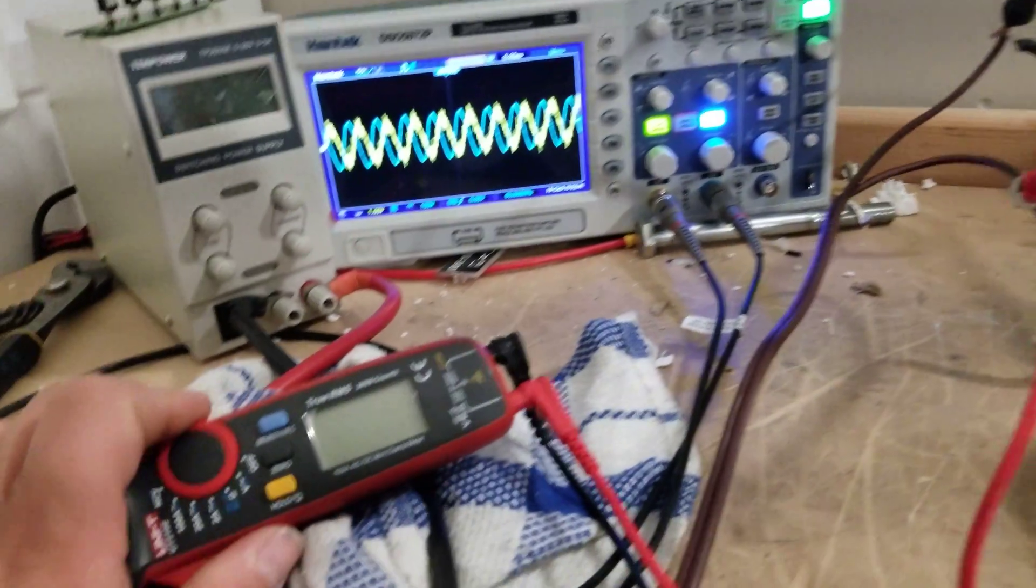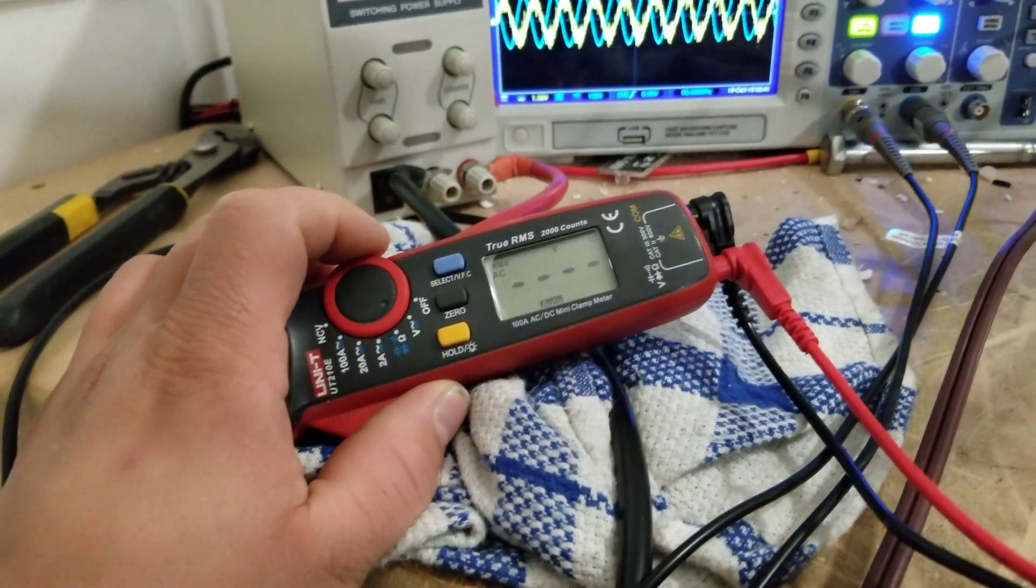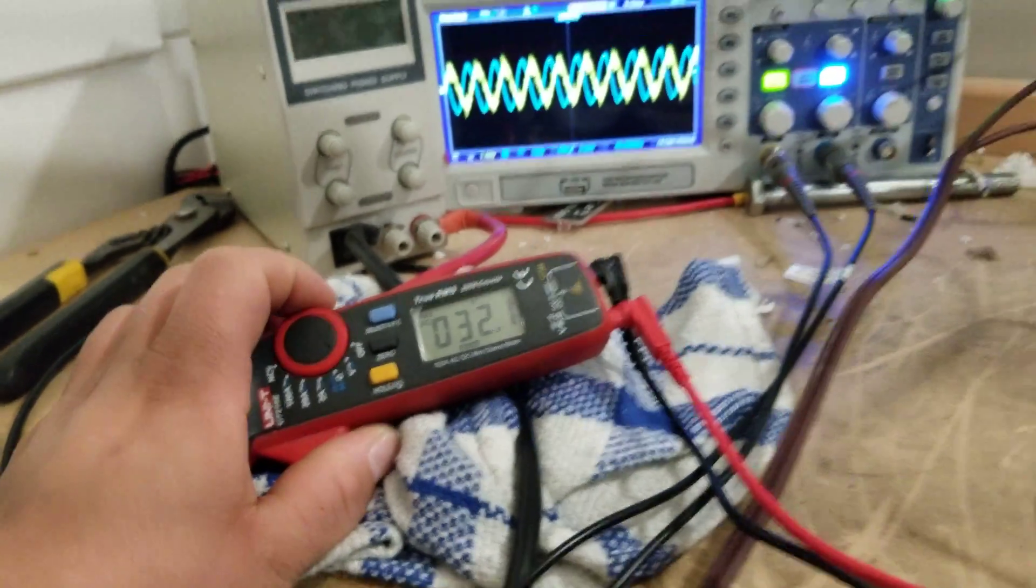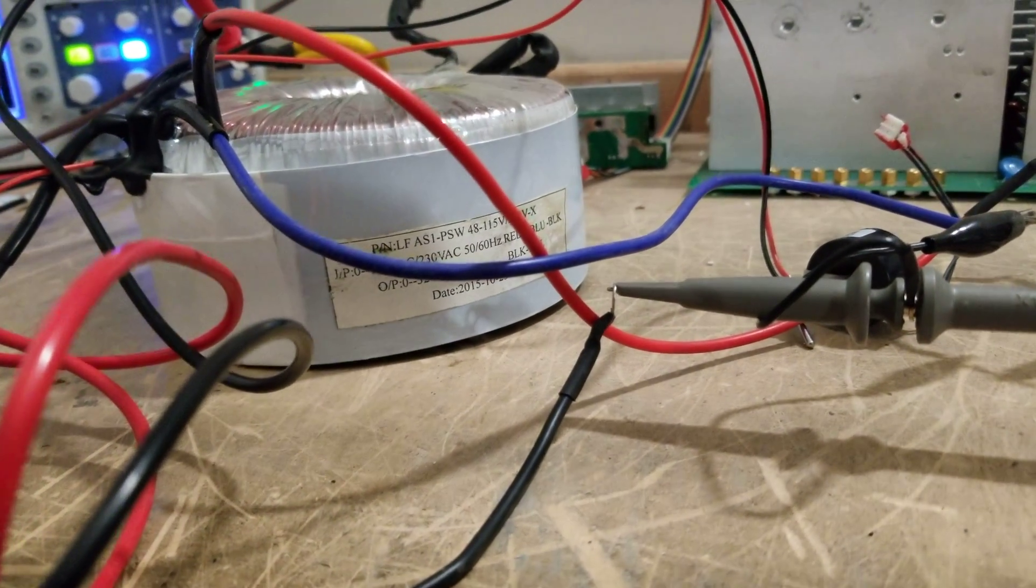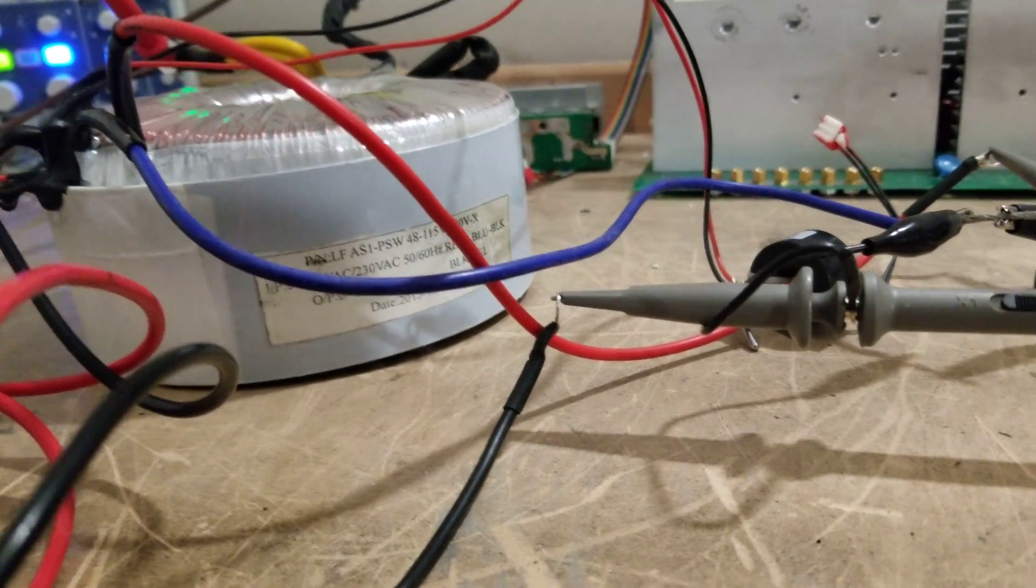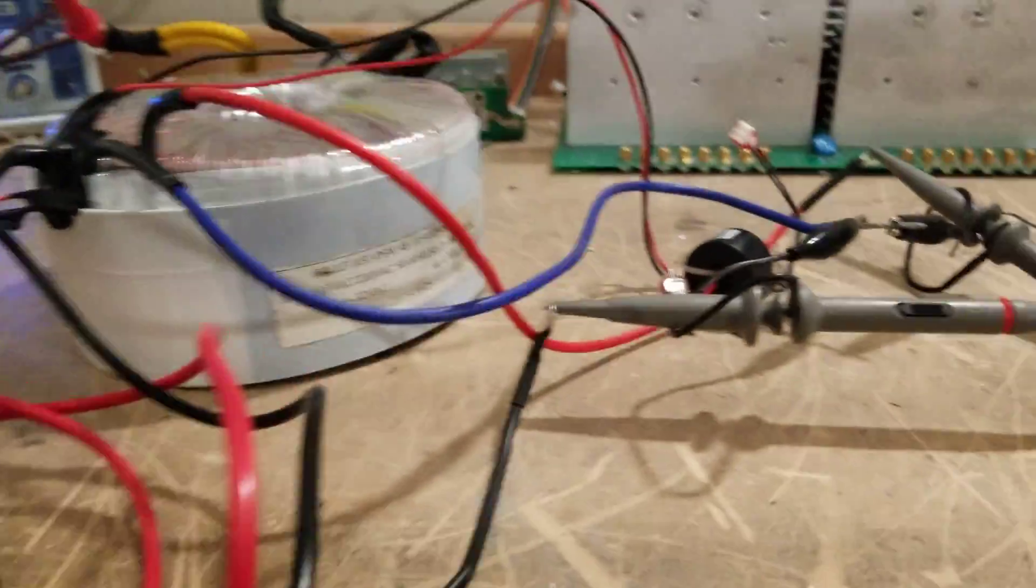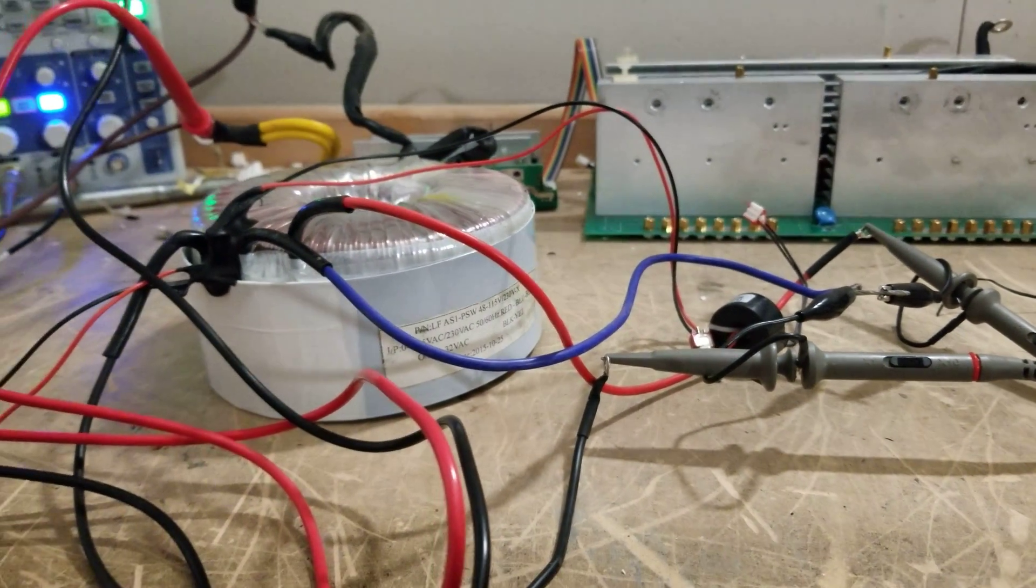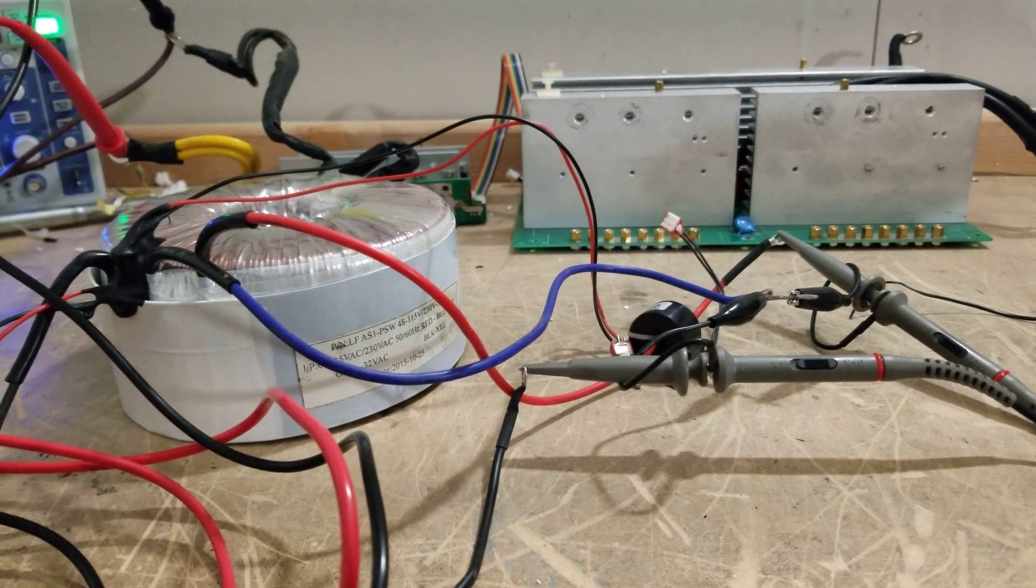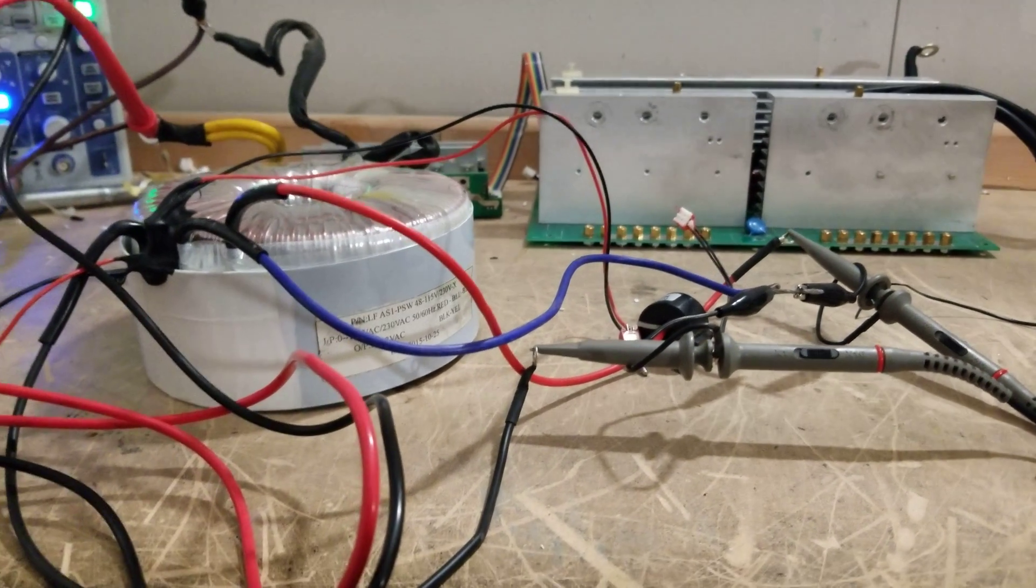Something happened, either it was damaged internally or whatever. But I am putting 32.1 volts into it, so yeah, it's really strange. This transformer is going to need to be replaced. As I said, sometimes it works, sometimes it doesn't. There is a faint smell coming from the transformer and it does have a hum to it. That leads me to believe that there's something internally damaged with it.